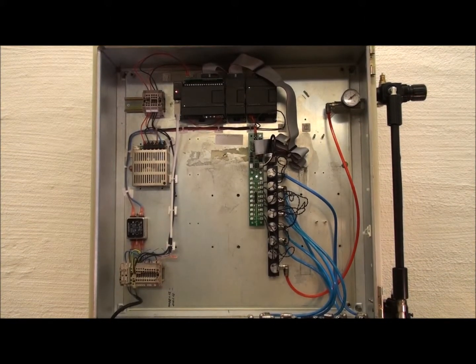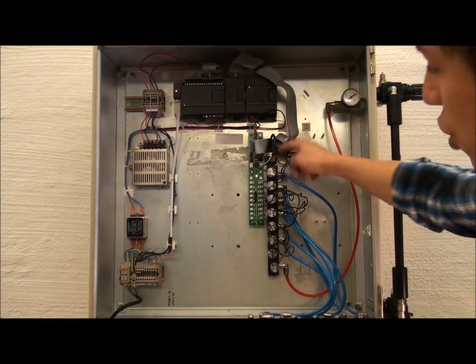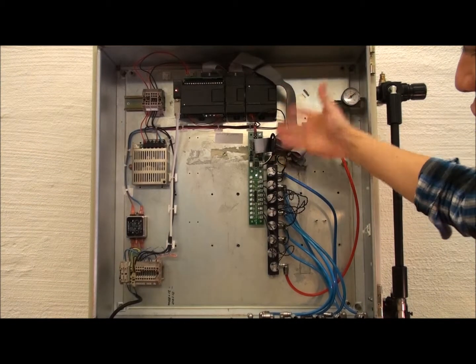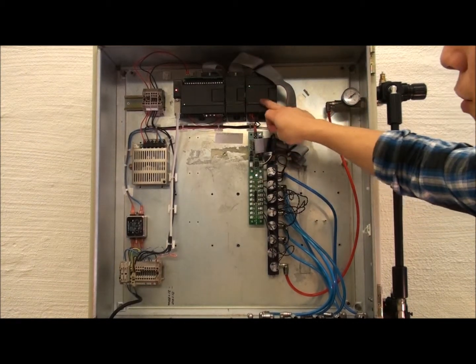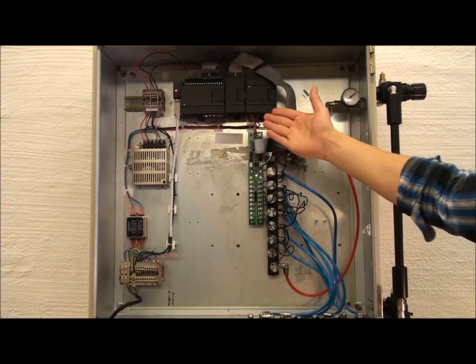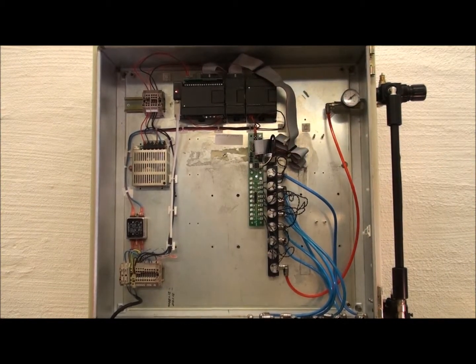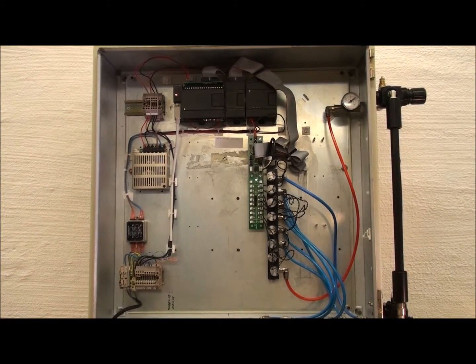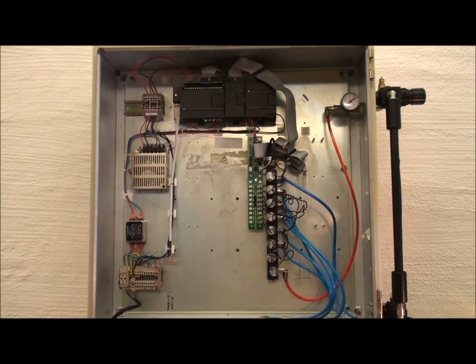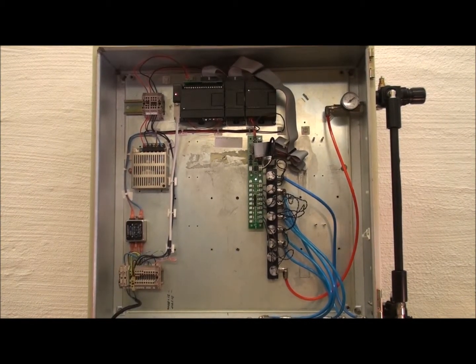The only reason you should calibrate the system is if you have changed the pressure sensor, you have changed the I/O modules, or you have changed the PLC itself. But in a normal situation, you don't need to calibrate the system because it doesn't uncalibrate by itself.